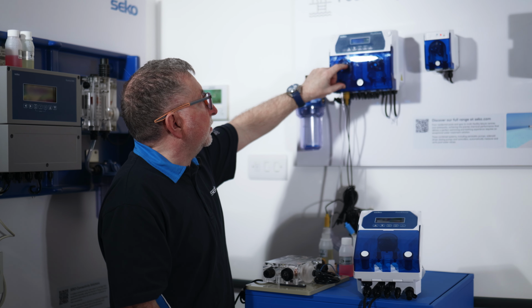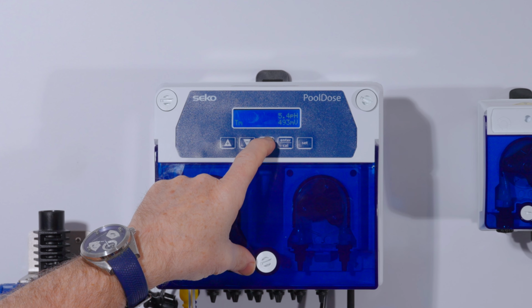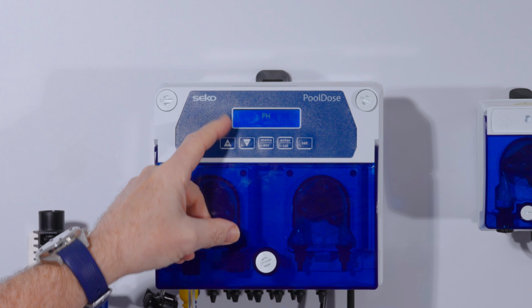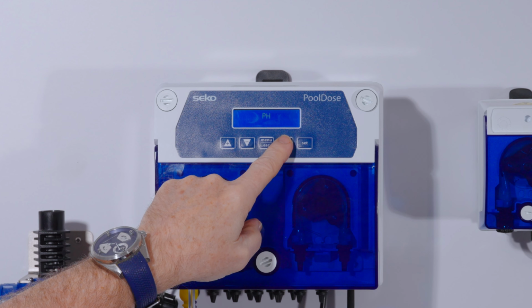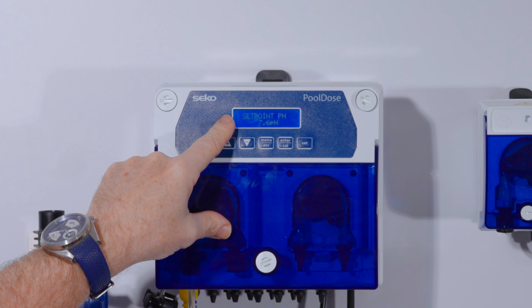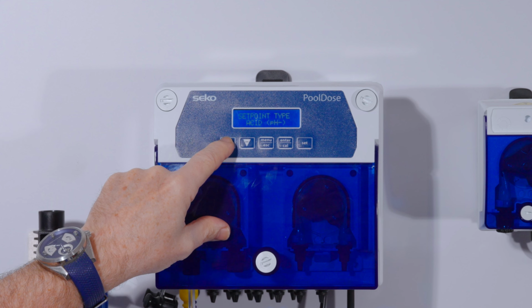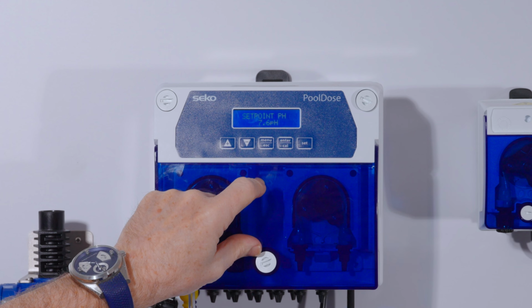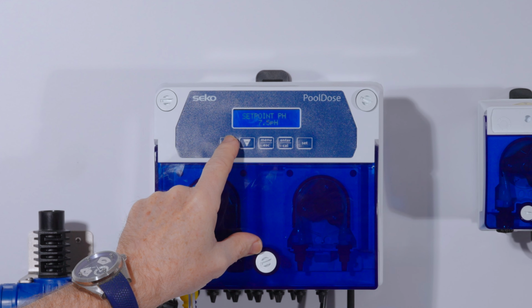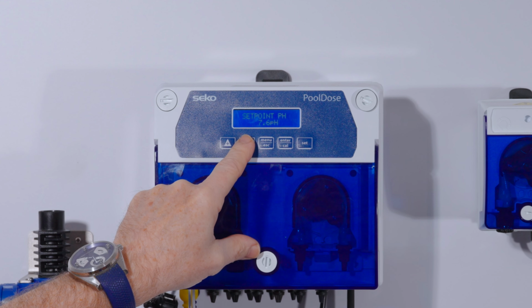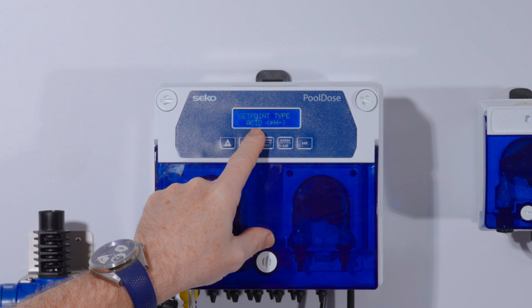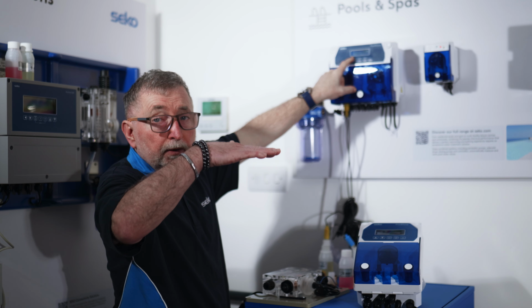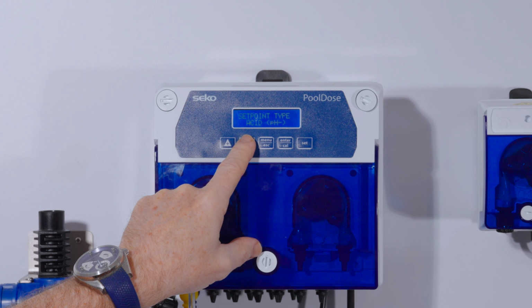So, setting up the unit, back into the menu once again. And if we take pH for an example, we enter the menu and we first have the set point, which we can adjust using the up or down buttons, but we have to enter the value, make that flash before we can make any changes. After the set point, we have the type of chemical we're dosing for acid to bring the pH down, which would be the common one.